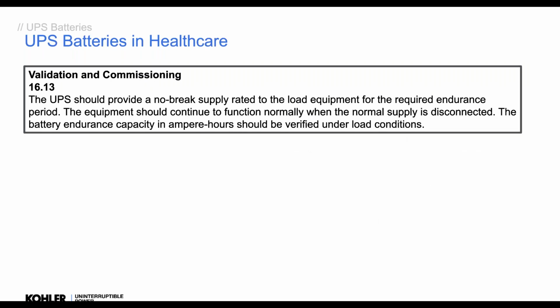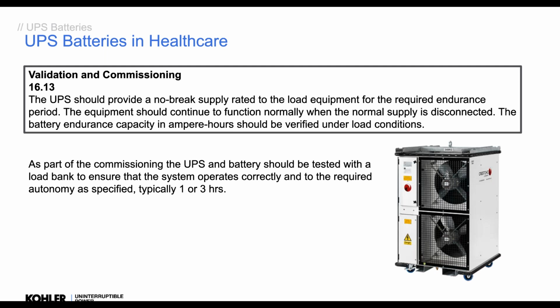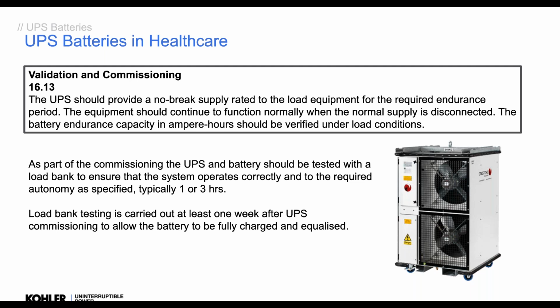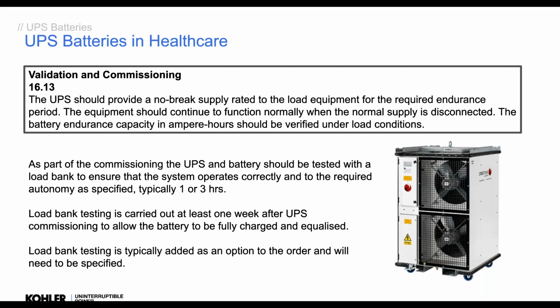All right. So the UPSs should be commissioned and validated. This means that we will typically come back after commissioning. We go to site, build the battery, commission the UPS, get it on charge, come back in a week's time with a load bank, put on the full load, turn the mains off, and prove it does the autonomy you require. For healthcare, this should be done. It's in the HTM and it should be done. Typically, this is an option, so again, you have to specify that you want this, because it will then be added onto the job and be done. It's always worth doing to prove that the supplier has actually given you what you asked for. But HTM is a requirement.